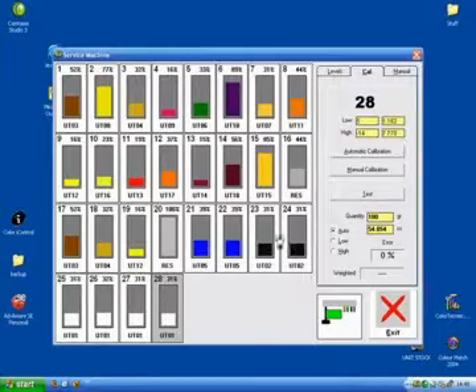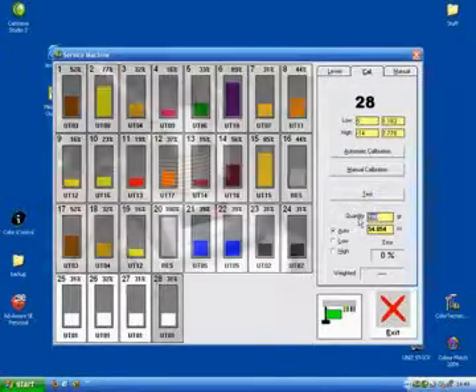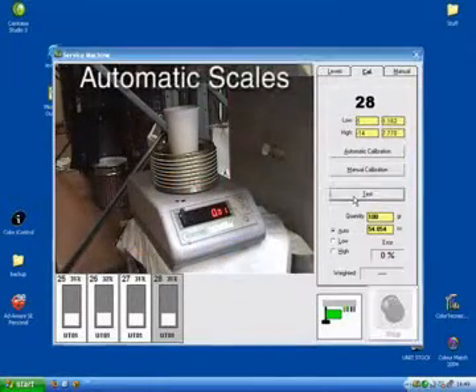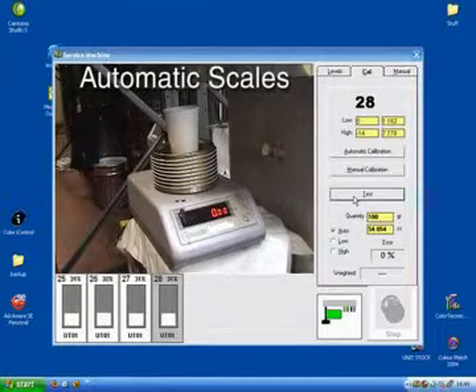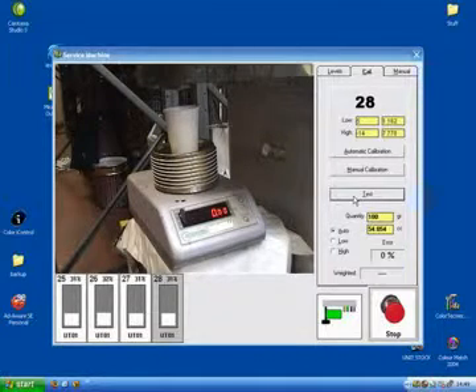The machine has 2 dispensing speeds, high and low. If we put 100 grams into the test box and click the test button, it will dispense 100 grams of colorant at high speed. After it's finished, the amount the machine actually dispensed will appear in the weighted box, along with the percentage of error in the error box.